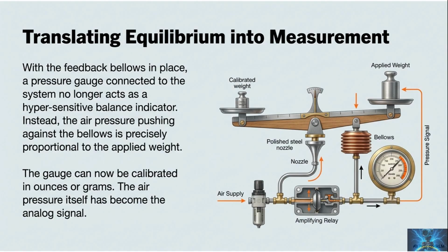With the feedback bellows in place, the pressure gauge stops being a twitchy balance indicator. The bellows pressure becomes proportional to the applied force needed to hold the mechanism in balance. That means the air pressure itself becomes the analog signal. Once it is stable, you can calibrate the gauge in real engineering units tied to the input force. The key idea is simple. Stable balance equals predictable measurement.